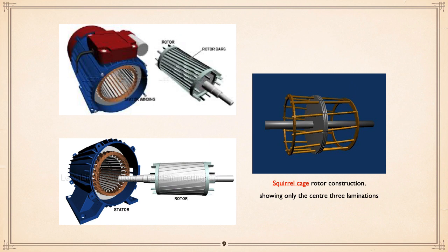Let's take a look at that further. There's your rotor, there's your stator. Now, when you first go to start the motor, let's say it's an 1800 RPM motor, the field within the stator is turning at 1800 RPM.